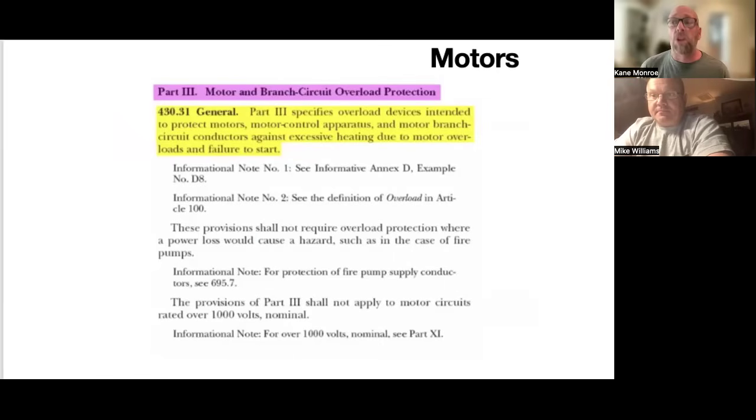No, sir, that's overcurrent. Overcurrent is your fuses. Overload is, have you been around heaters where you walk up to the panel and you push a reset button because the heater tripped or the overload tripped? Have you ever had that situation? I can't say that I have.